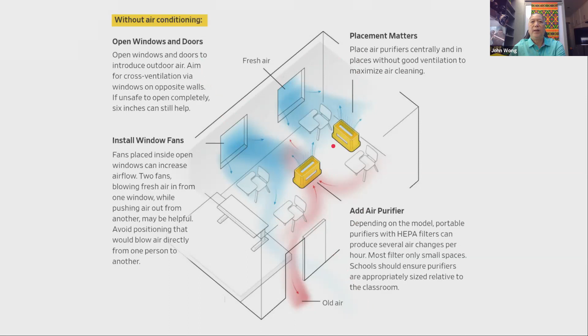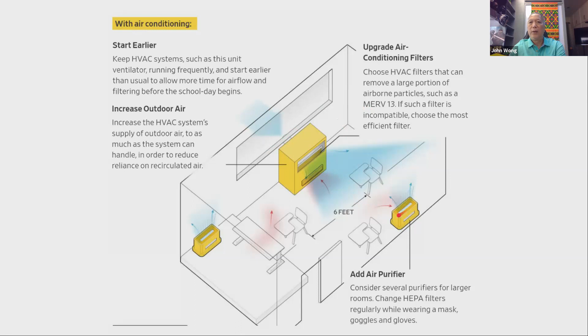If you have a room with air conditioning, run the air conditioning earlier than people arrive, and run it for about 30 minutes after they leave. If the air conditioning allows, allow more outdoor air to come in, so open the exhaust a little so that you're always constantly introducing outdoor air. You can also upgrade your filters to use MERV 13, which are high performance filters, and you can also add air purifiers.